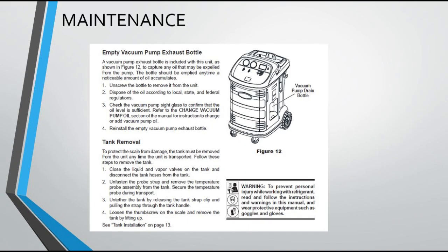Empty vacuum pump exhaust bottle. A vacuum pump exhaust bottle is included with this unit, as shown in Figure 12, to capture any oil that may be expelled from the pump. Unscrew the bottle to remove it from the unit. Dispose of the oil according to local, state, and federal regulations. Check the vacuum pump sight glass to confirm that the oil level is sufficient. Refer to the Change Vacuum Pump Oil section of the manual for instruction to change or add vacuum pump oil. Reinstall the empty vacuum pump exhaust bottle.